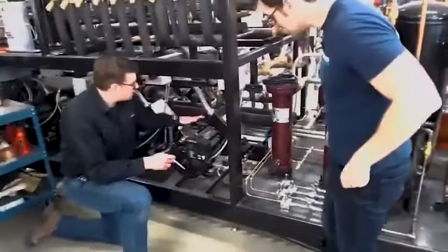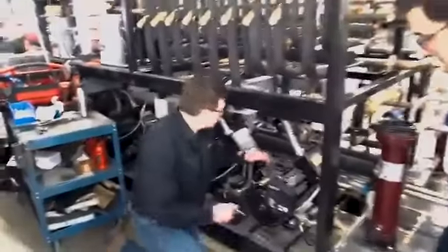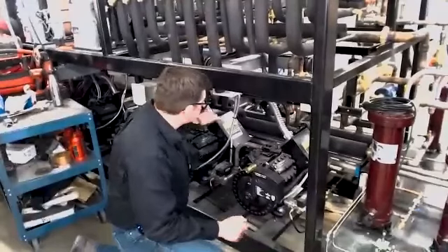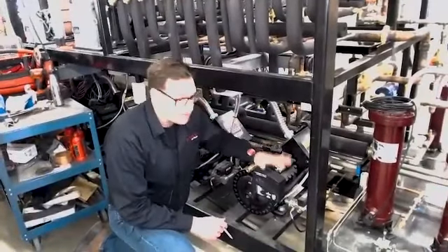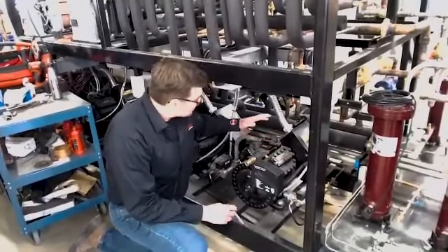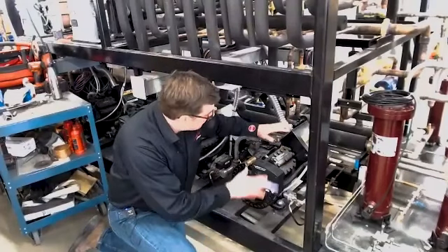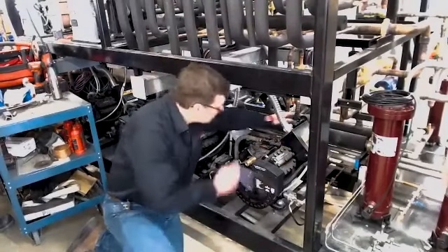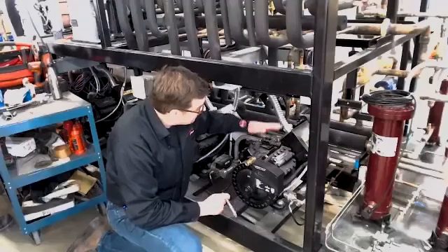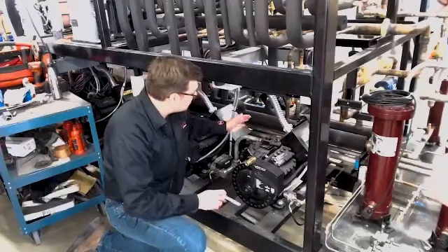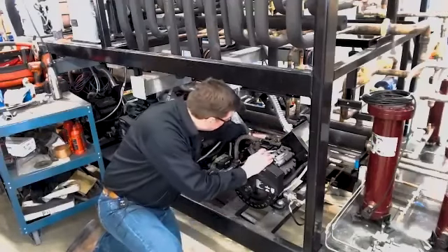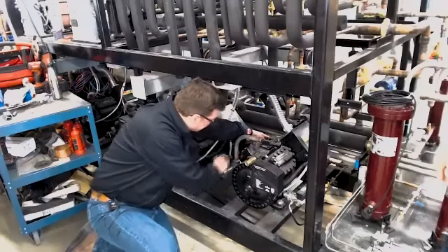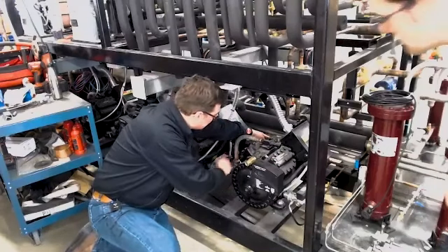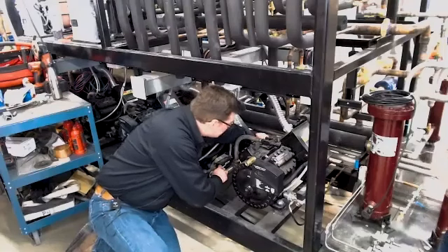Compressors, if we want to take a look - these Copeland compressors, this is a mix of 11s, 15s, 20s, and 29 horsepower on this specific rack. But if we need to change a compressor, we've got our service valves. We've got a stainless steel service valve here, and this is really important. We have a ball valve in the back on our manifold line, which we can talk about another time, but we can isolate our compressor here.